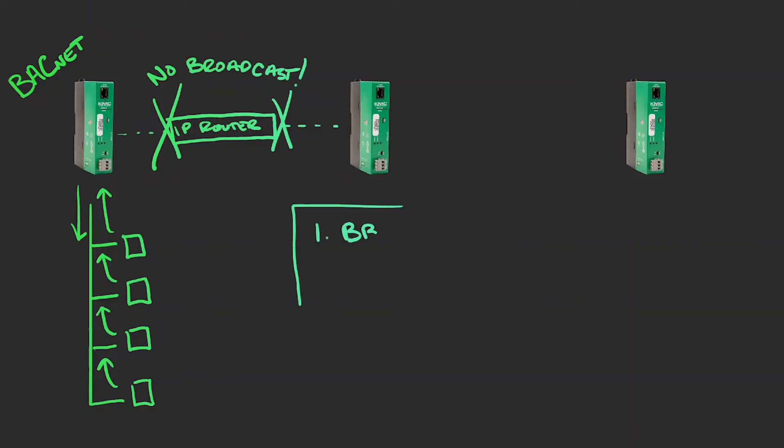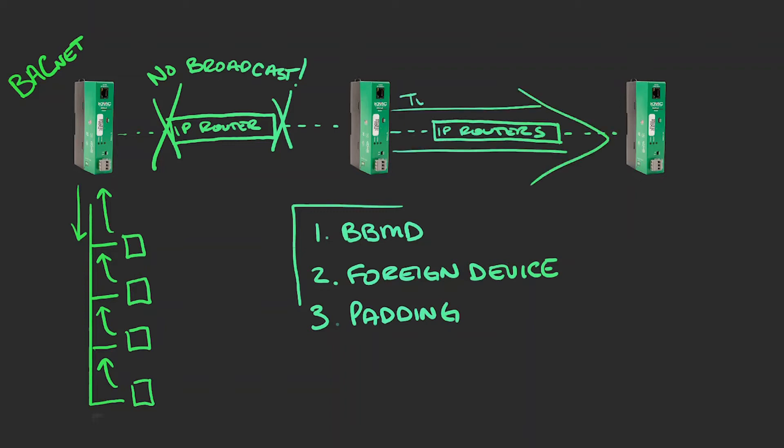There are three ways to configure a BACnet router to work around this issue: BBMD, foreign device, and padding. In all three methods, BACnet routers encapsulate broadcast messages into unicast messages that IP routers will forward. This concept is called tunneling and has been done in the IT networking world for decades. There are many IP protocols that use a tunneling method to get from here to there on different subnets.